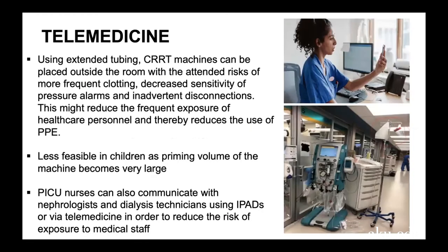One of the ways to limit exposure to your healthcare professionals is by using extended tubing. Set your CRRT machine outside the isolation room so that exposure to the patient is less. But of course, in children, sometimes it's not feasible because there's an attendant risk of more frequent clotting, decreased sensitivity of pressure alarms, and inadvertent disconnections. So in children, the priming volume of the machine might become very large and it might not be feasible, but if doable, this is one way to limit exposure to your healthcare professionals.